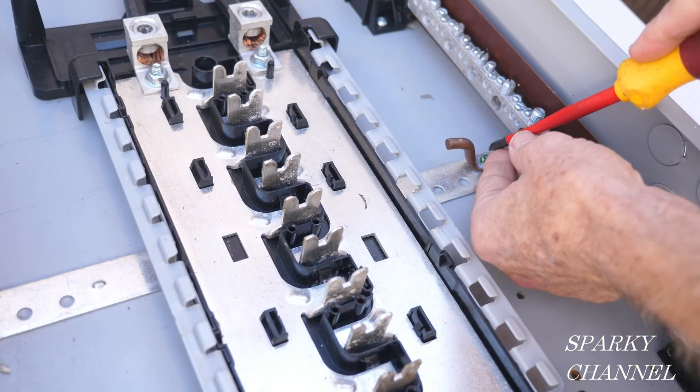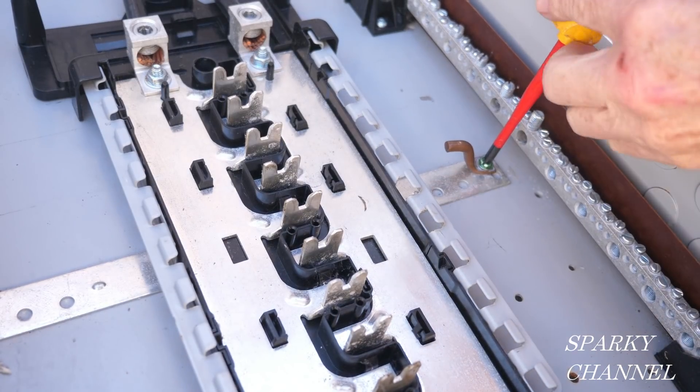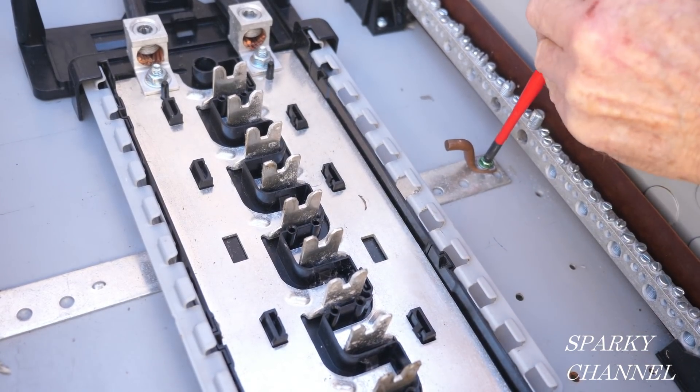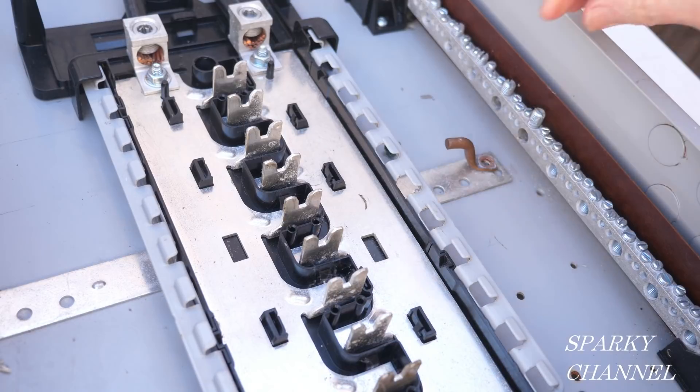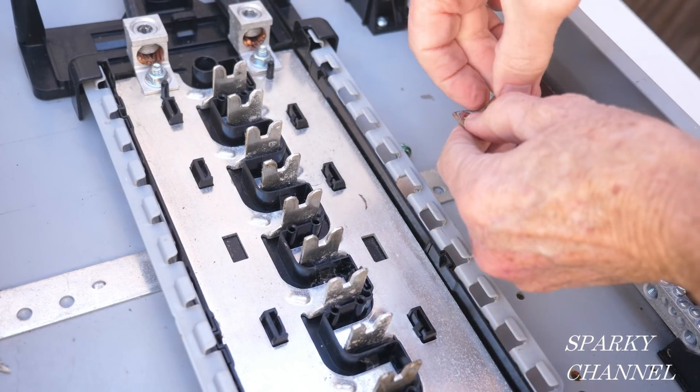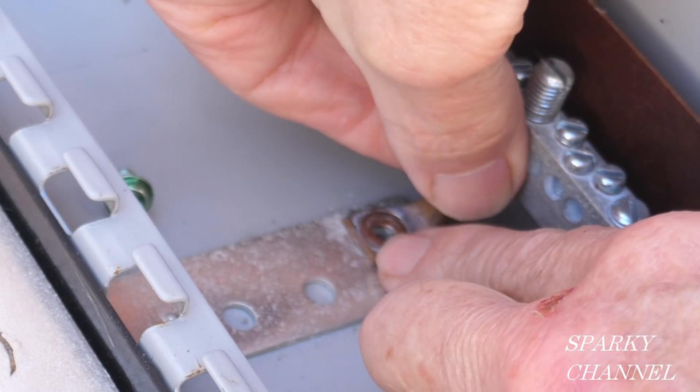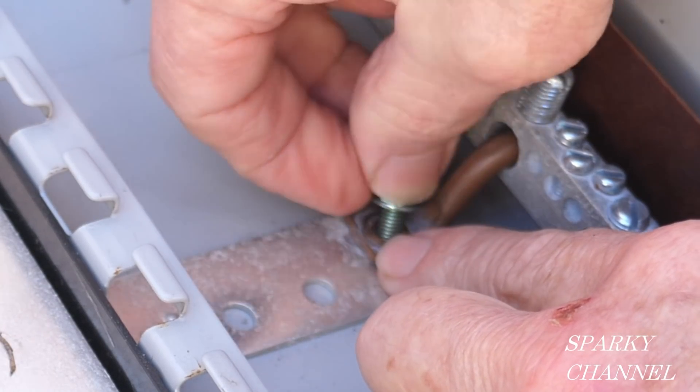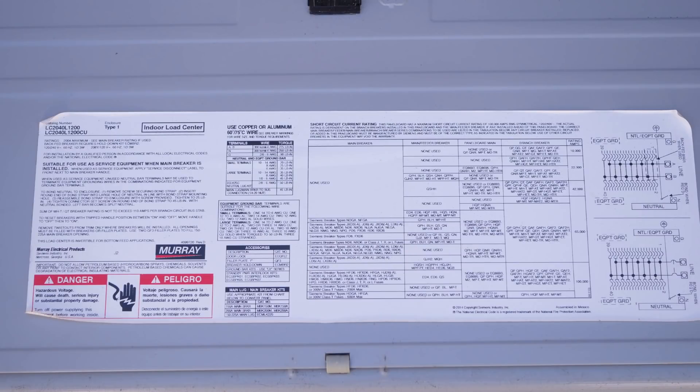As a clue, I'll loosen up this green bonding screw in the Murray load center and turn it toward the neutral bar. Notice that it fits into one of the large terminals on the neutral bar.